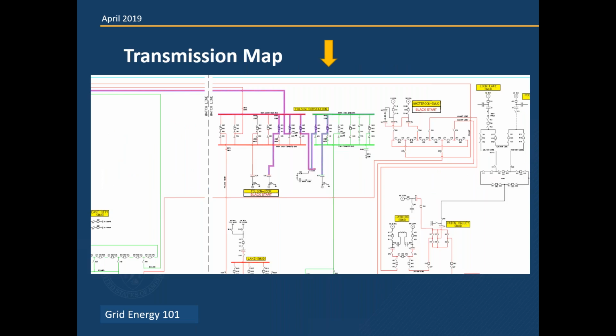So here's where our arrow was in the last slide, and we've taken a look at Folsom Substation, which is a 230 to 115 kV substation, and it has three generators on it. They're owned by the Bureau of Reclamation, and they are our Black Start resource. One of my specialties is system restoration, and most utilities have a Black Start generator. What I mean by Black Start is they can start without power from the grid. When we lose voltage and frequency on the system and the system blacks out, then we have to start the system up, and we have a generator that's capable of starting without power from the grid. Normally, generators use power from the grid to start. But when we have no voltage and frequency, how do we do it? Well, we have sources built within the station to start it without power from the grid. Next slide, please.